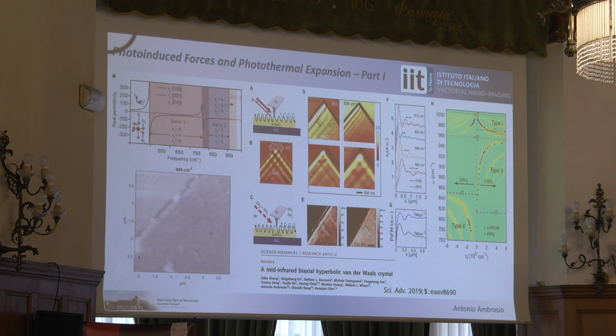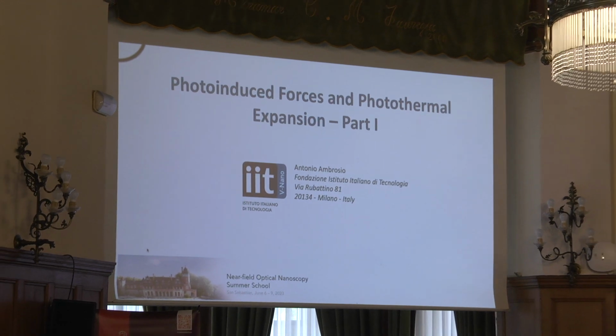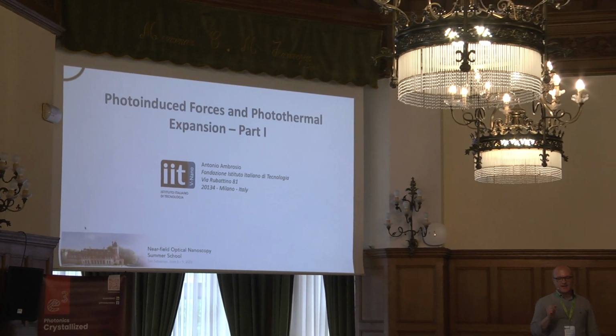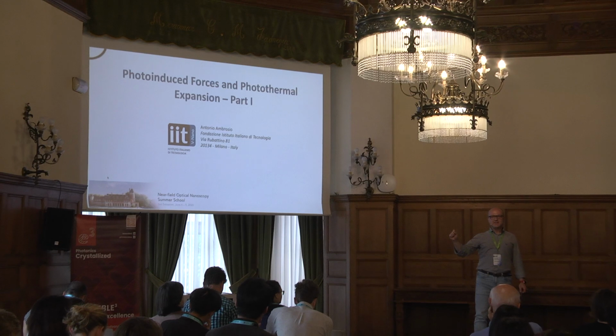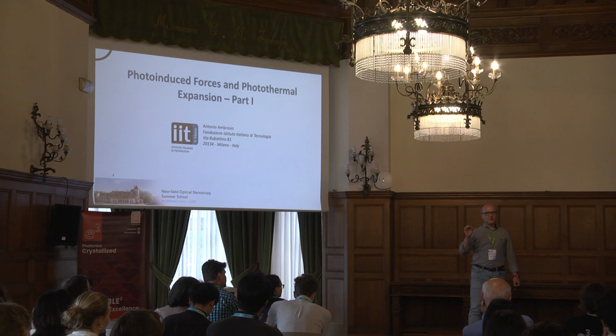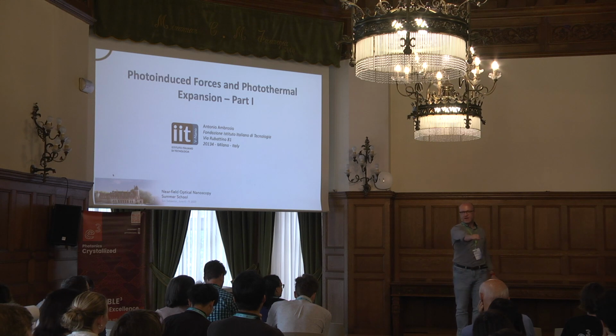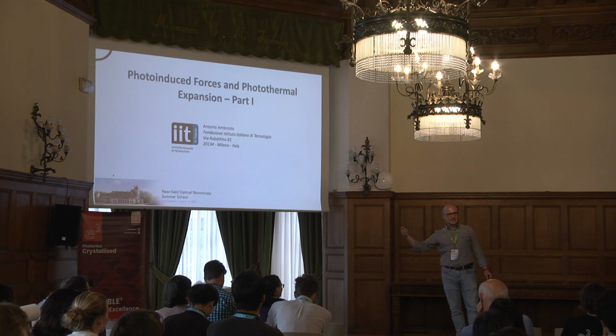Now, before I conclude, I think time is over. Just a comment about the NeaSPEC system. I think it's correctly implemented, and you even have the PLL that follows the frequency shift, so that you get rid of the material component. But take care: if you have to plan an experiment, all that the NeaSNOM so far gives you is a TTL. So it works for diodes, where you can plug in the TTL and modulate. It can work for QCLs, but if you have a laser like titanium sapphire, where you cannot plug in a TTL and make it modulate, you have to use an external modulator.